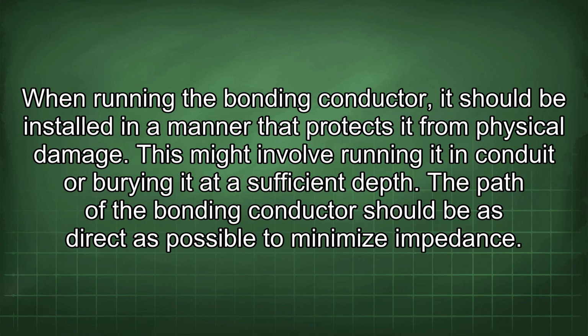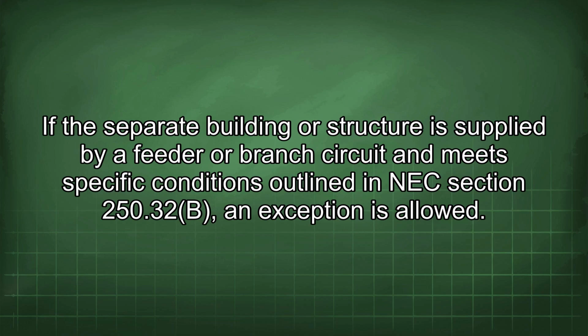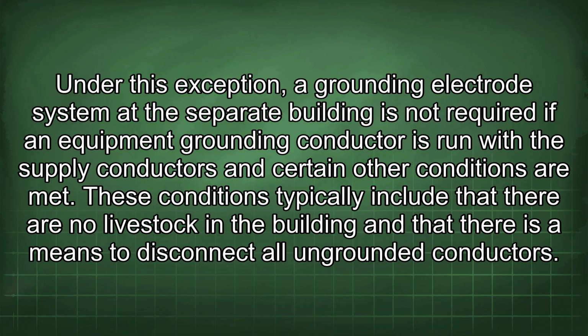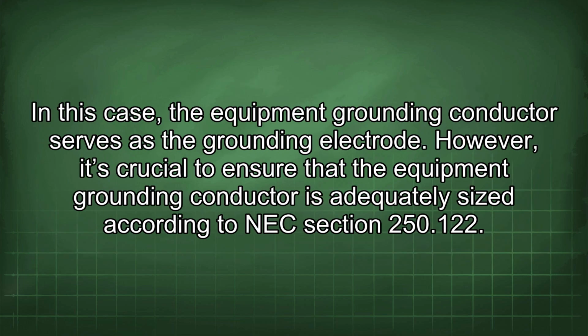When running the bonding conductor, it should be installed in a manner that protects it from physical damage. This might involve running it in conduit or burying it at a sufficient depth. The path of the bonding conductor should be as direct as possible to minimize impedance. If the separate building or structure is supplied by a feeder or branch circuit and meets specific conditions outlined in NEC section 250.32(B), an exception is allowed. Under this exception, a grounding electrode system at the separate building is not required if an equipment grounding conductor is run with the supply conductors and certain other conditions are met. These conditions typically include that there are no livestock in the building and that there is a means to disconnect all ungrounded conductors. In this case, the equipment grounding conductor serves as the grounding electrode.